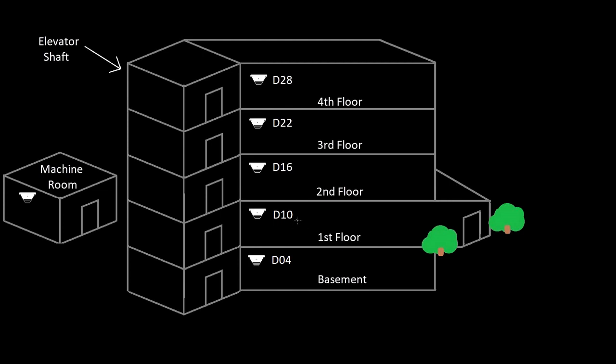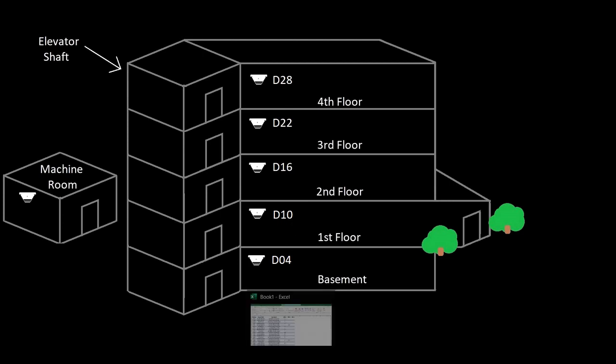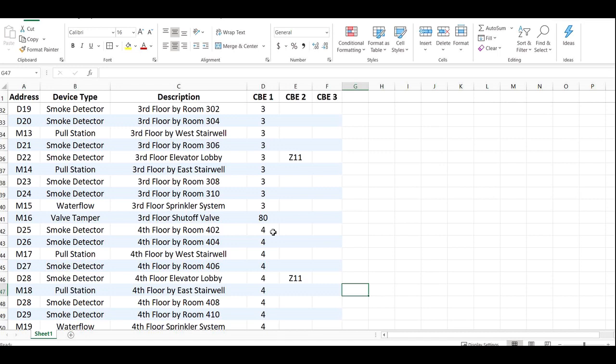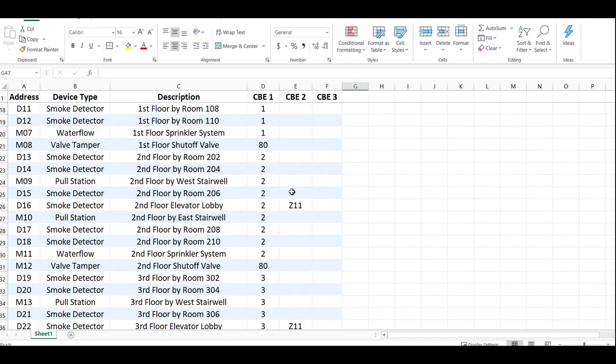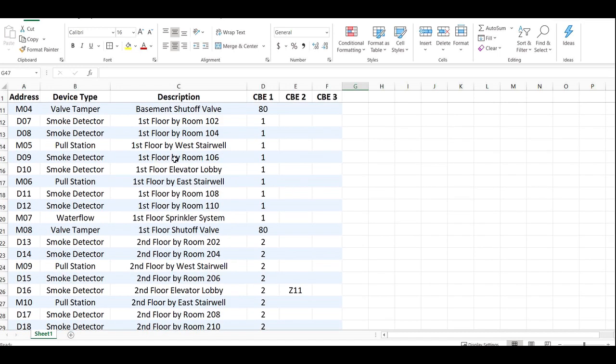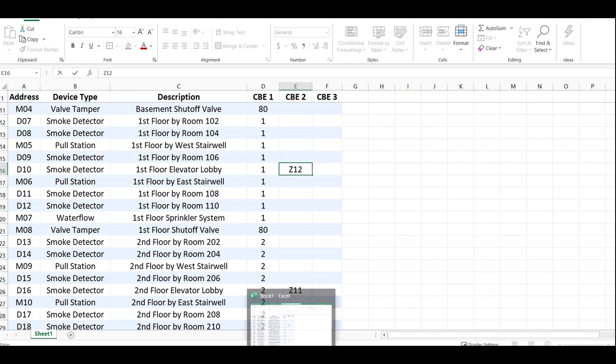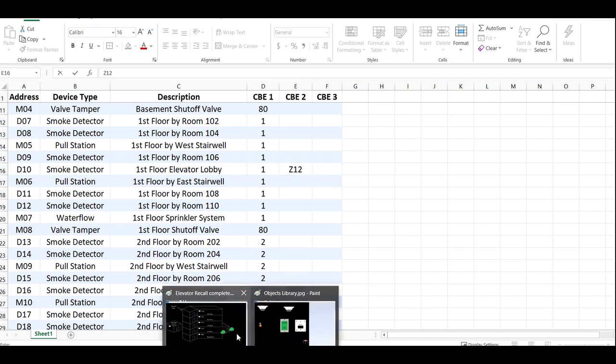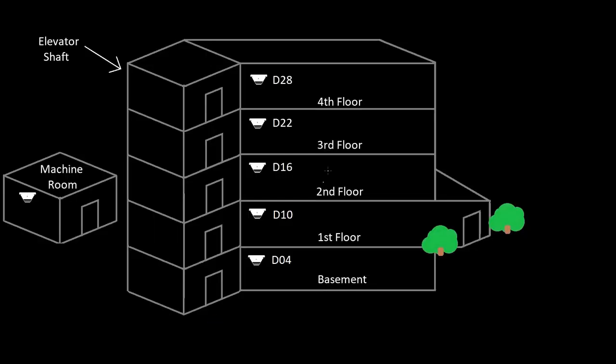Those are all done. Now for our first floor, let's make that zone 12. First floor elevator lobby here is going to be zone 12. What we're going to end up doing is mapping that to a relay, so zone 11 is what's going to turn on the primary relay, zone 12 is what's going to turn on the alternate relay.